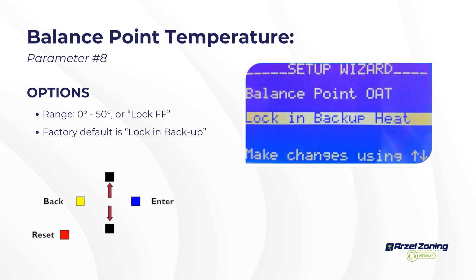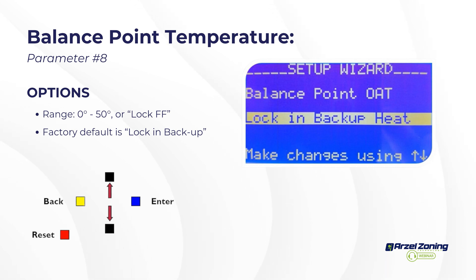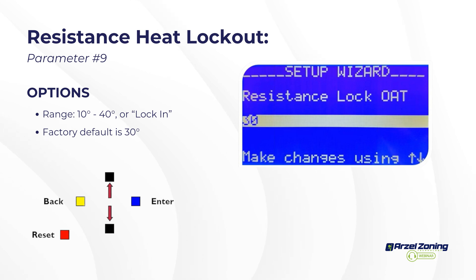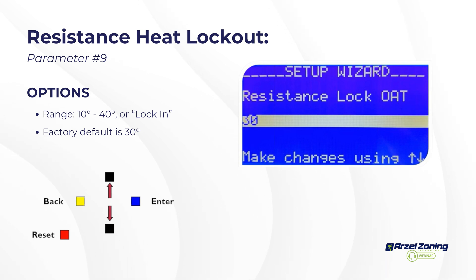Balance point OAT is the changeover temperature from heat pump to fossil fuel backup. If you don't have a heat pump, set it to 'lock in backup' — that's the factory default. If you have a heat pump, once the outdoor temperature reaches the balance point, the heat pump is disabled and only fossil fuel backup runs. The lock OAT efficiency setting for all-electric applications disables electric backup heat until a specific outdoor temperature is reached, saving customers electricity.